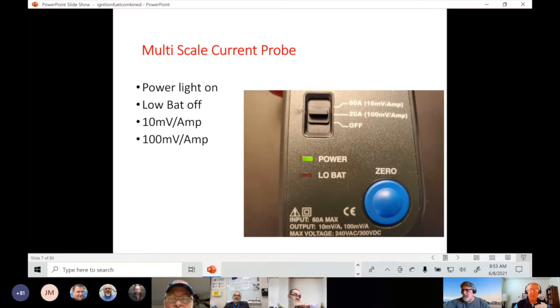This one has two different scales. What does that mean? Look at the picture and see the 20 amp scale, with 100 millivolts per amp in parentheses. That means if this current probe is clamped around a wire that has 1 amp flowing through it, it will generate a 100 millivolt signal.